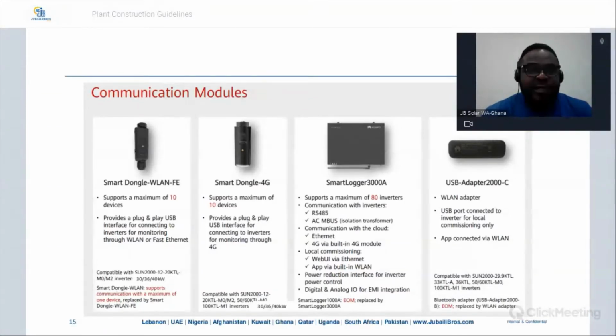These smart dongles can offer you the opportunity to connect up to 10 inverters in a synchro if you are synchronizing inverters together. If the inverters have batteries, like residential inverters, then you can do a maximum of three in a synchro using these smart dongles. But if the number of inverters becomes too much, let's say 15, 20, 30 inverters, like a CNI project or a big utility scale project, these smart dongles will not work.